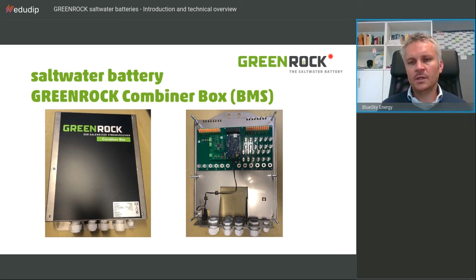The second functionality is that we have electrical shunts in there measuring the performance of each stack, so we can see and determine if the whole system overall is in balance. It's a monitoring system on stack level, especially for bigger installations with longer or larger systems, so we can see if all stacks are in balance and getting the same energy distribution.